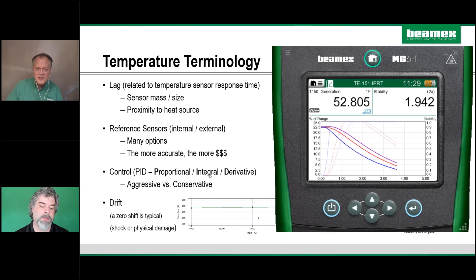But one thing to note is if you can use the internal reference for your calibration, it makes life much easier for the technician. So that kind of gets back to the tolerance, which is on the next slide.